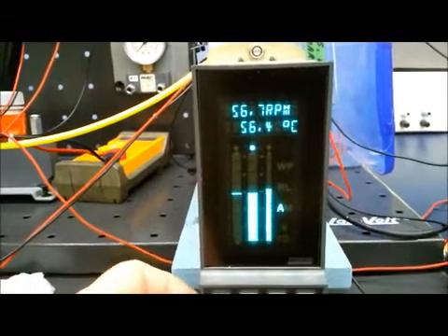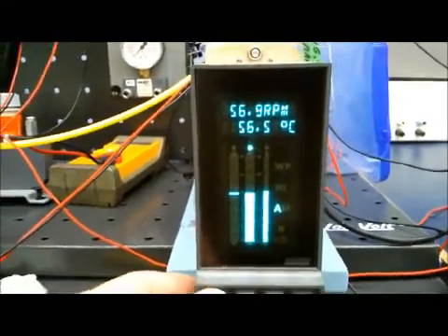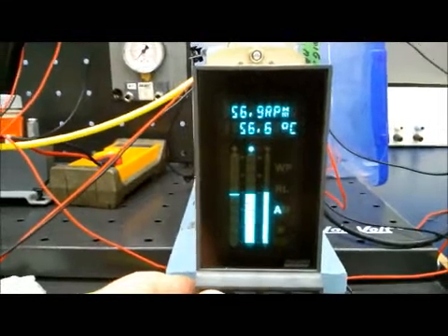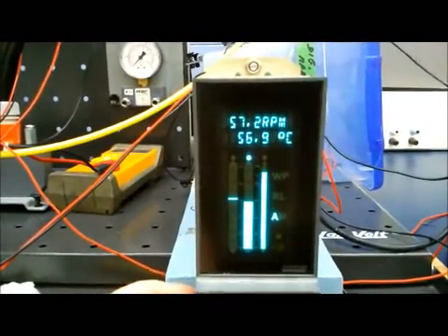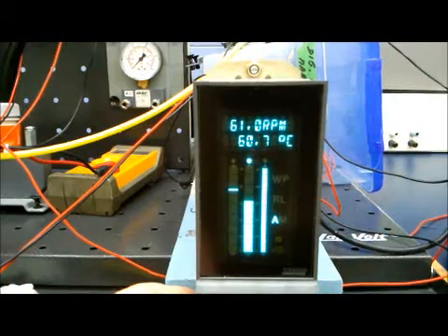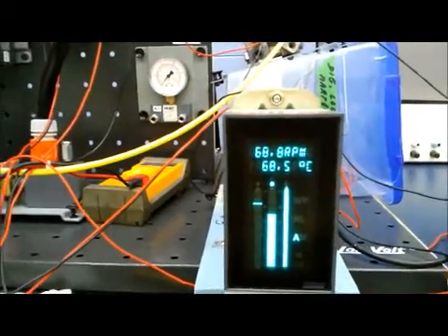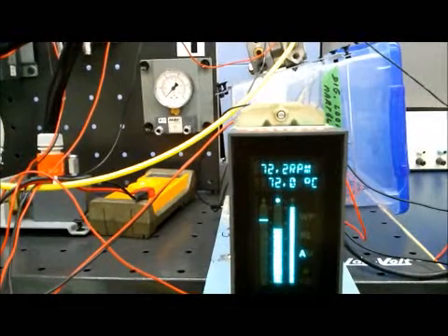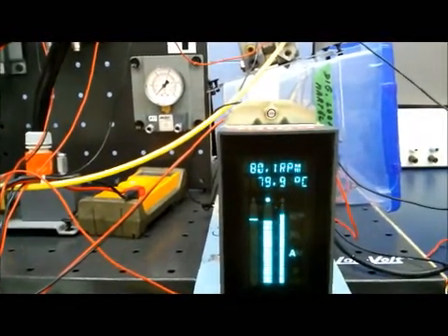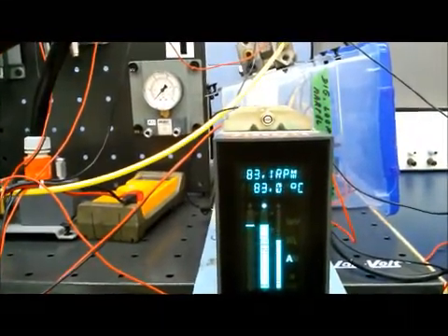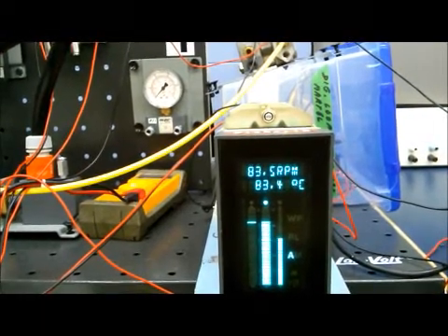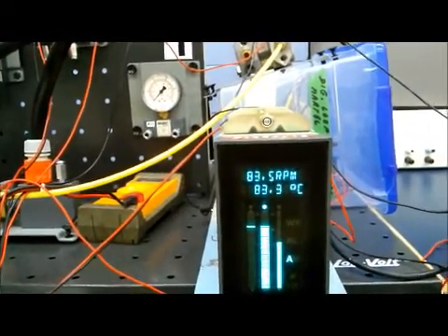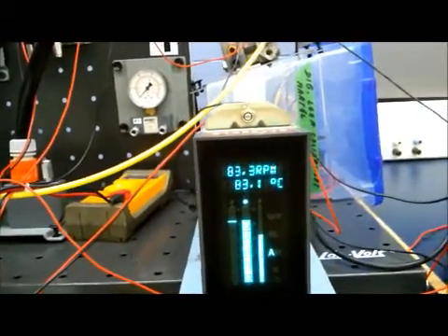I'm going to make another 20% increase change. There's a little over 20% and up comes my level. And there, the output's gone down. Seems to be performing okay. That's proportional only.